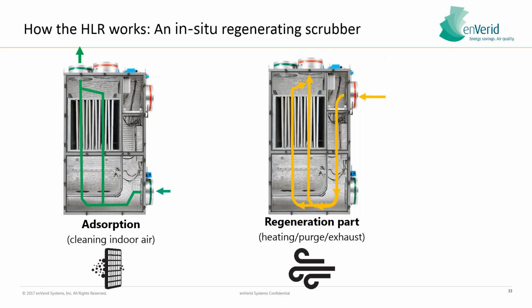at around 250 CFM. So we're purging this unit of CO2-laden air once we heat up the system above 130 degrees Fahrenheit to purge that air outside of the building through the toilet exhaust or directly outside the space. It's just environmental air, so you don't need to do anything special with it, but you do need to account for that, and we typically do that during unoccupied hours.